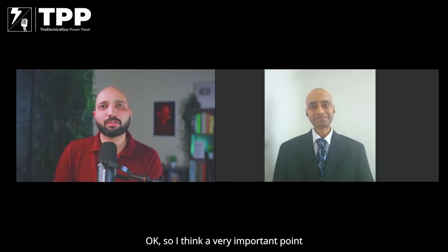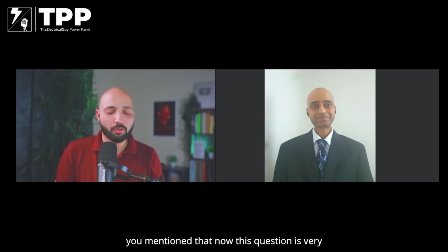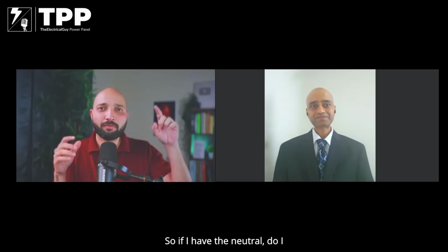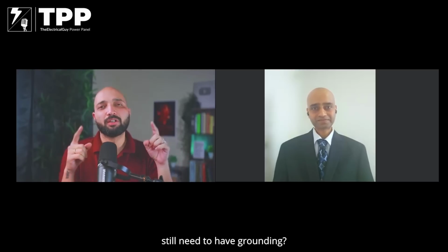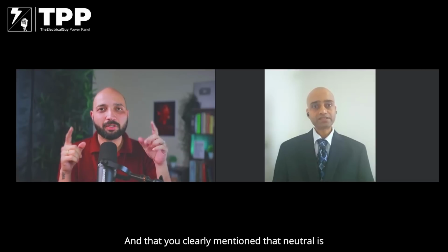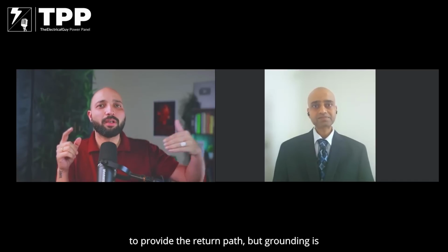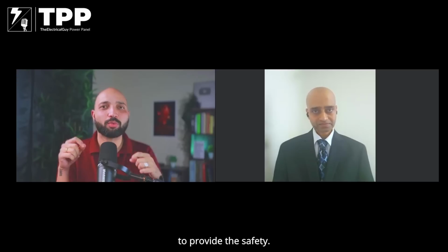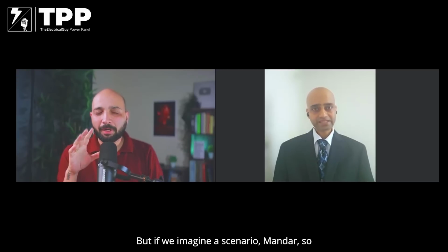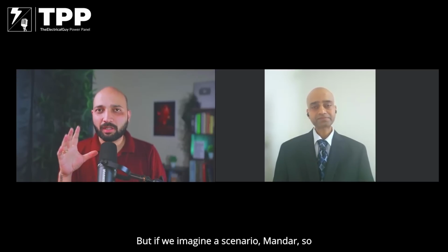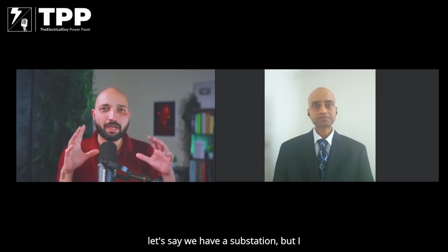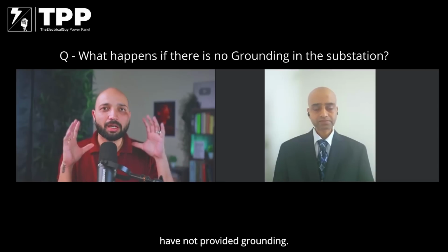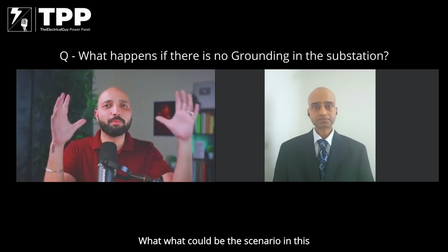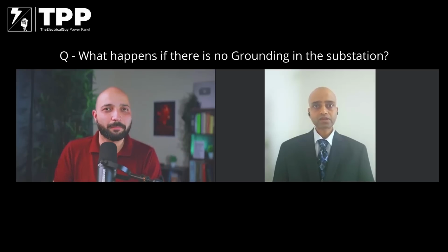Okay, so I think a very important point you mentioned, and this question is very commonly asked: if I have the neutral, do I still need to have grounding? You clearly mentioned that neutral is to provide the return path, but grounding is to provide the safety. Maybe if we imagine a scenario, Mandar, let's say we have a substation, but I have not provided grounding. What could be the scenario in this case?